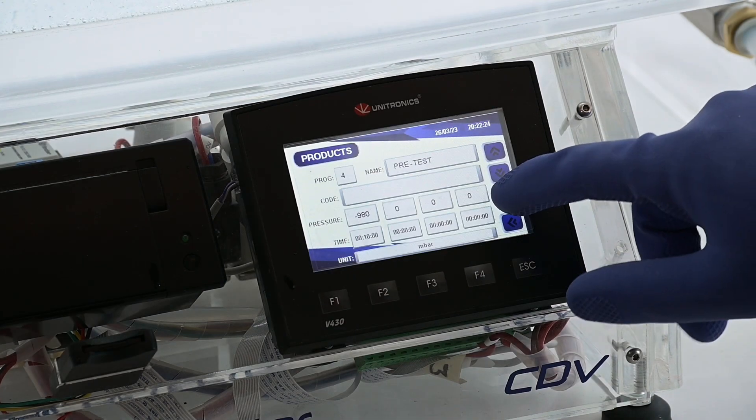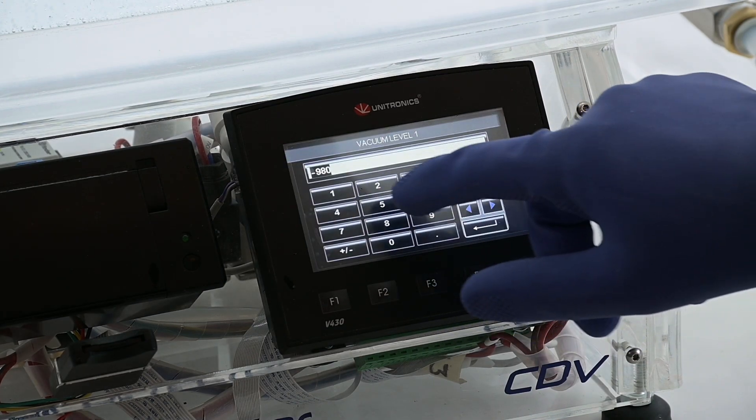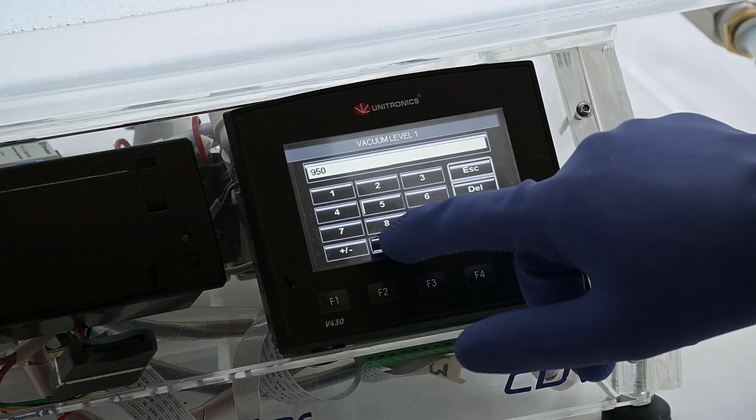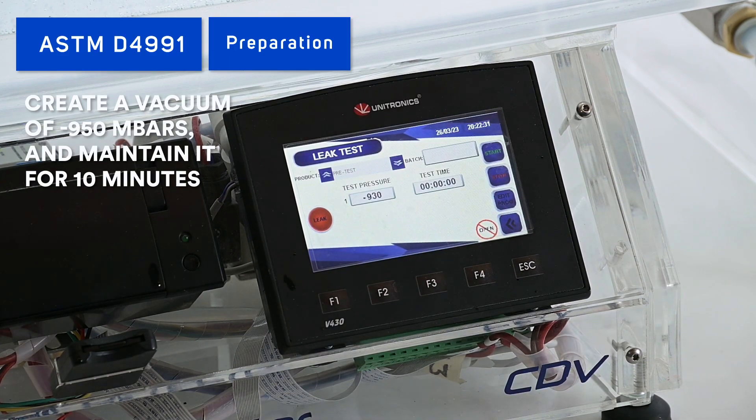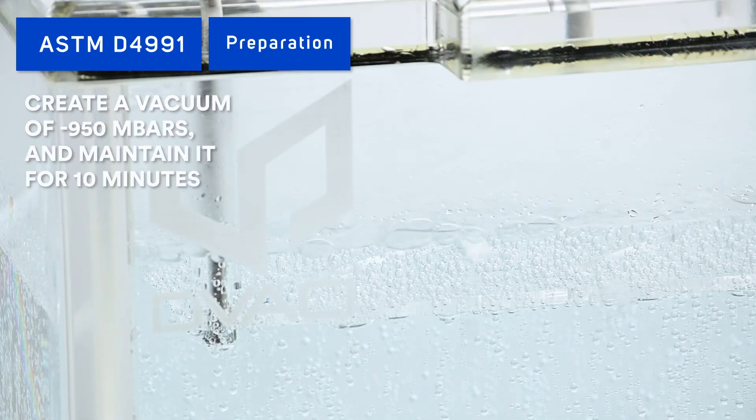To take things further, the test method has a specific focus on removing air dissolved in the immersion fluid before running the experiment, by creating a vacuum of minus 950 millibars and maintaining it for 10 minutes.